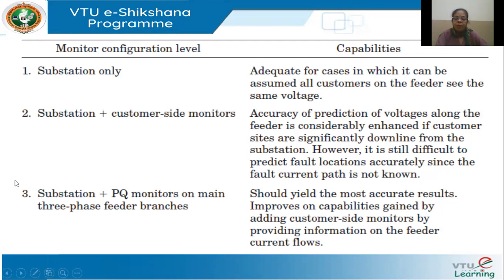So what is done is I have substation monitor plus PQ monitors on the main 3-phase feeder branches. On the main branches of the feeder. So more than 2 monitors. So this should yield more accurate results and it improves the capabilities gained by adding customer side. So along with this, you also have customer side monitors.